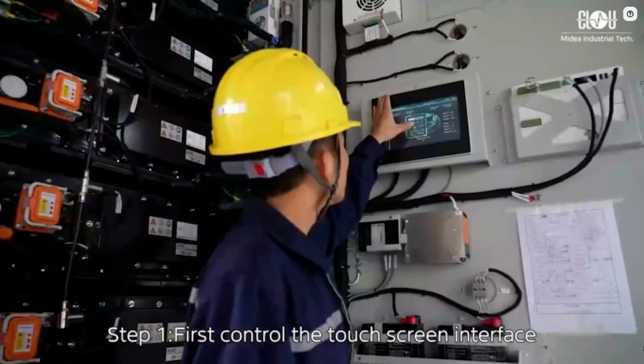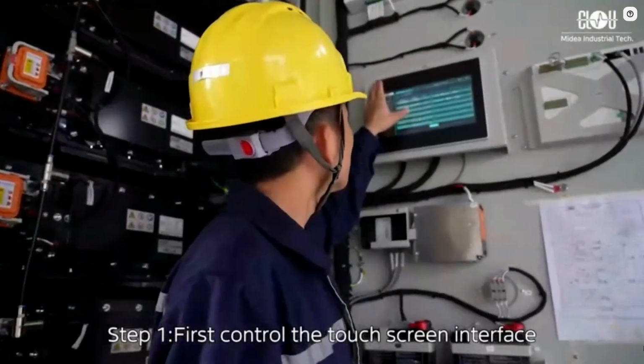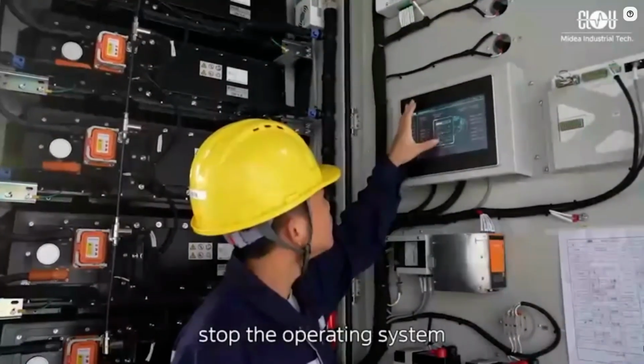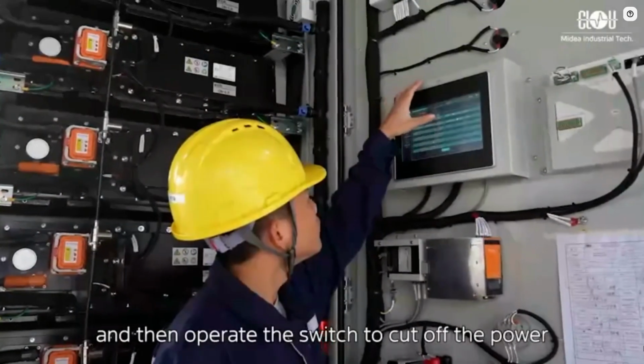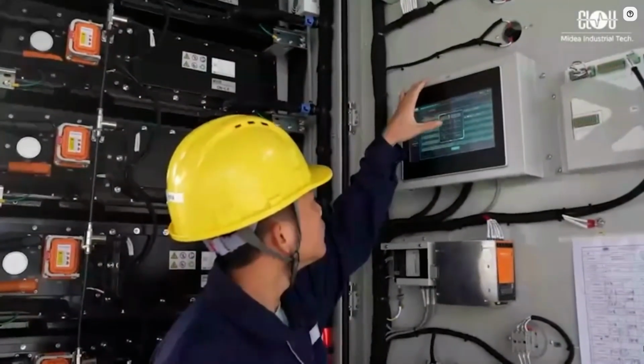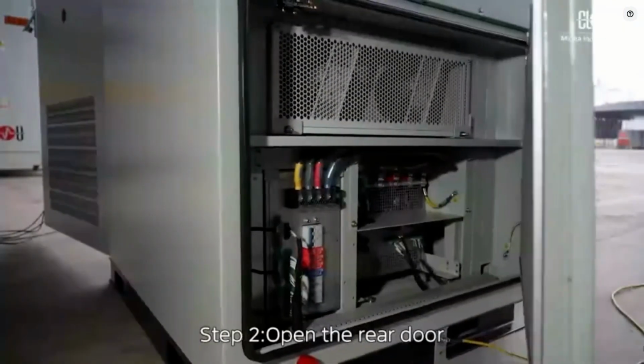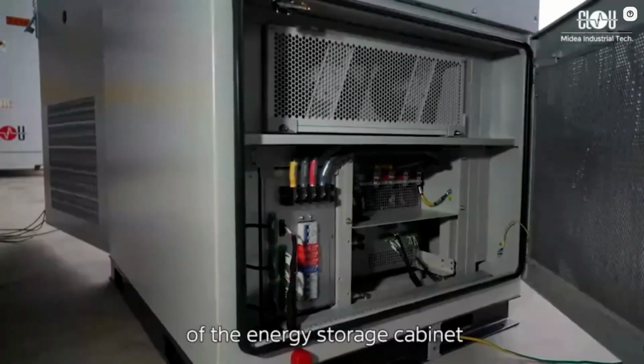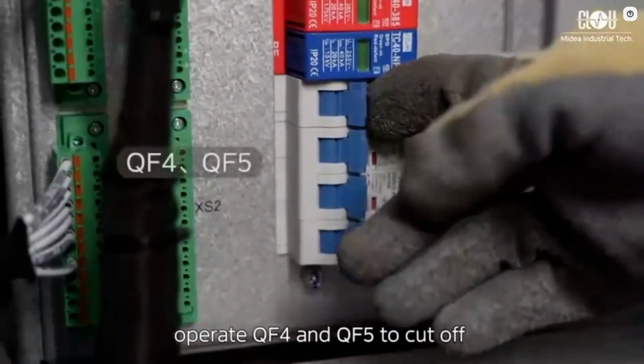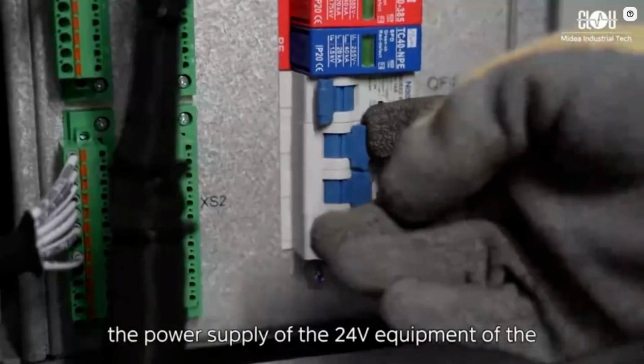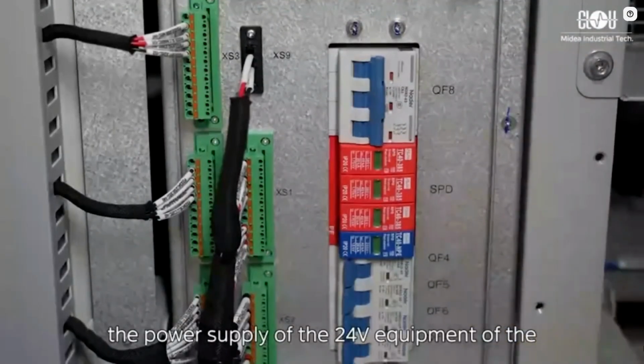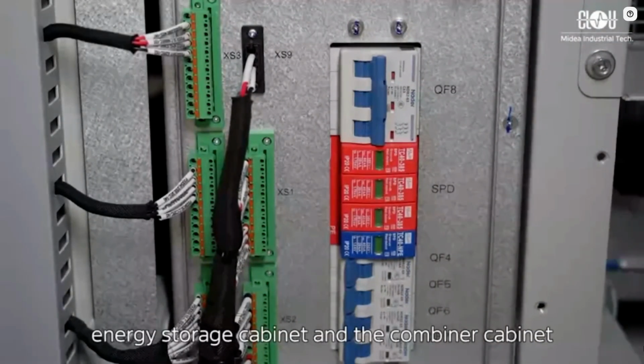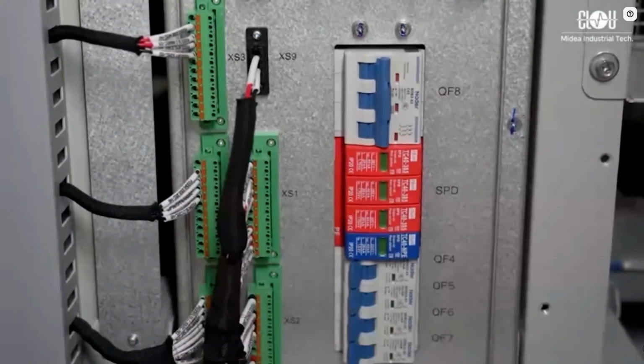Power cutoff operation. Step 1. First control the touchscreen interface. Stop the operating system, and then operate the switch to cut off the power. Step 2. Open the rear door of the energy storage cabinet. Operate QF4 and QF5 to cut off the power supply of the 24V equipment of the energy storage cabinet and the combiner cabinet.